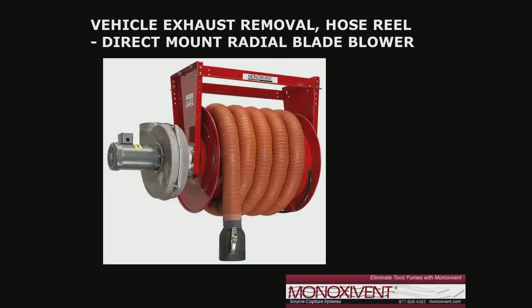Again, in this particular picture it shows a spring hose reel. It doesn't matter if it's spring or motorized, but what I'm showing here is the direct mount fan. We just recently did a project in Cleveland at a high school vocational school that was teaching the kids how to work on automobiles. They had 18 bays, each bay had a single reel, and each reel had a direct mount fan. We also incorporated the DMS HR switch, which is direct mount switch to hose reel. As the children would pull the hose down to put it on the tailpipe, the fan would start automatically. And when they would allow the hose to recoil, the fan would turn off automatically. You want to make sure the fan is on during those processes, so that took the decision making away from the kids to make sure the system worked as needed.